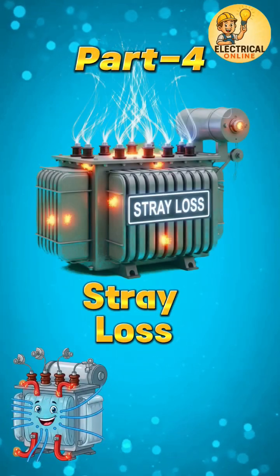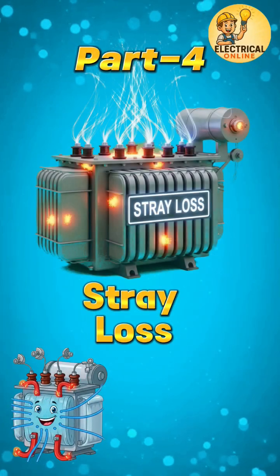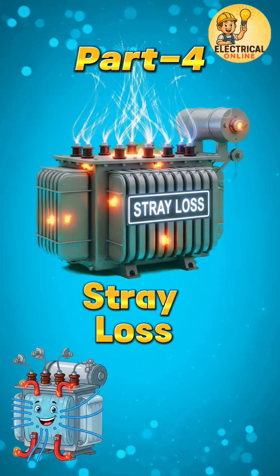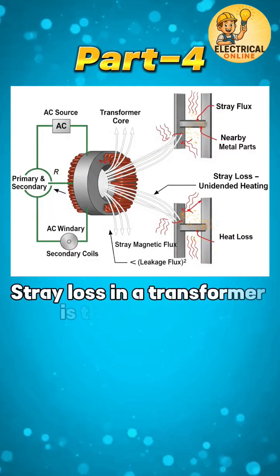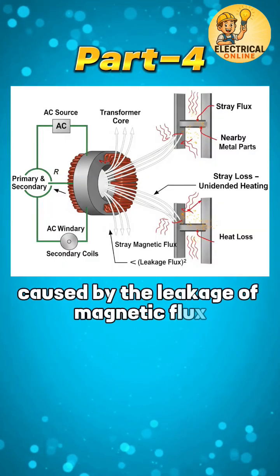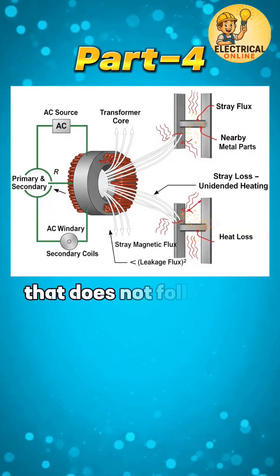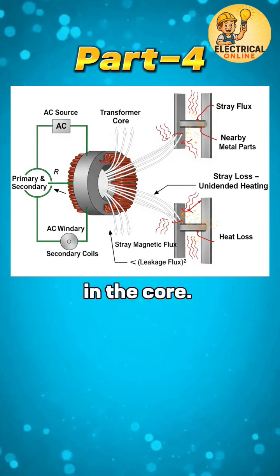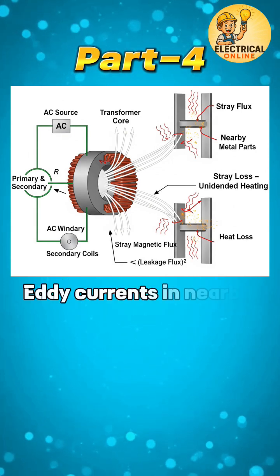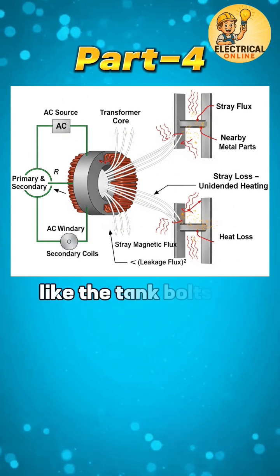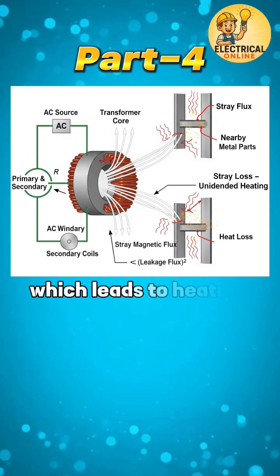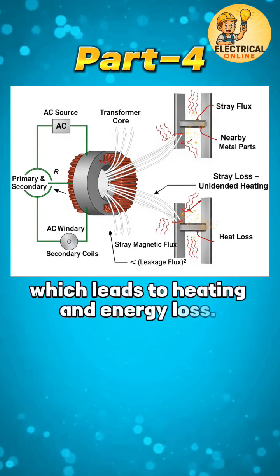Now let's talk about a magnetic rebel: stray loss, caused by flux that escapes the core. Stray loss in a transformer is the power loss caused by the leakage of magnetic flux that does not follow the intended path in the core. This stray magnetic field induces eddy currents in nearby metallic parts like the tank, bolts, or structural supports, which leads to heating and energy loss.